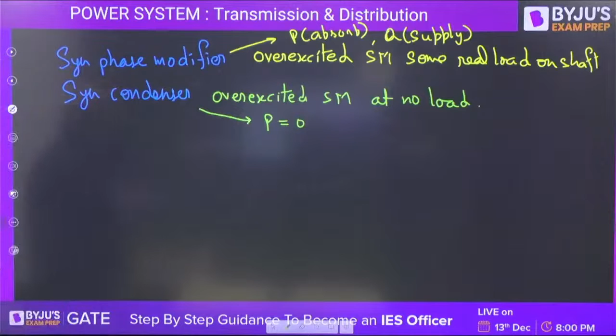What about the synchronous condenser? This is also an overexcited synchronous motor, but it is at no load. When it is at no load, P exchange is 0. There is no exchange of real power for the synchronous condenser. And Q is supplied. This is the basic difference between synchronous condenser and synchronous phase modifier. That is why there is no real power exchange. So it is supplying some lagging reactive power to the system.